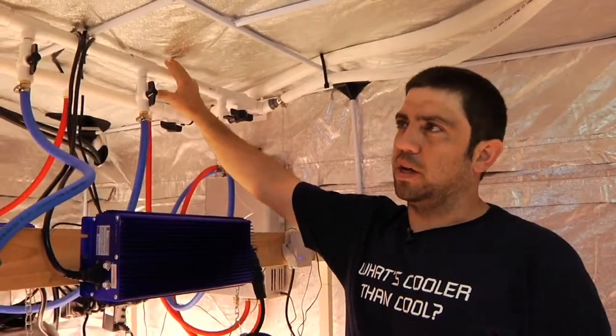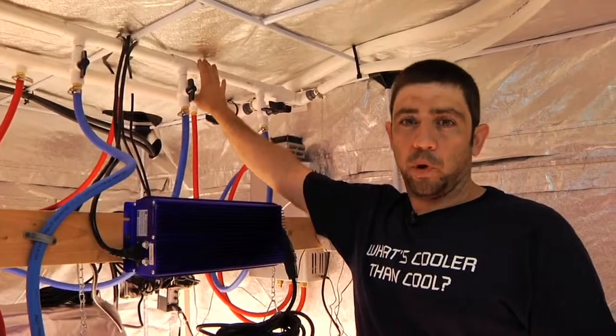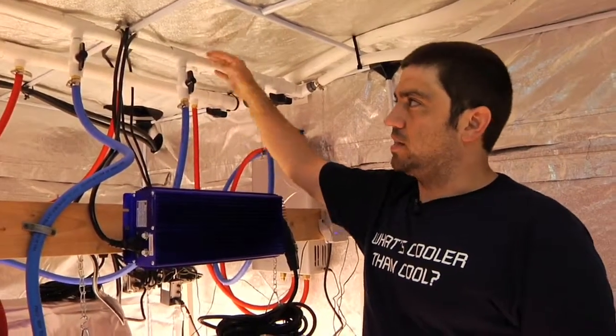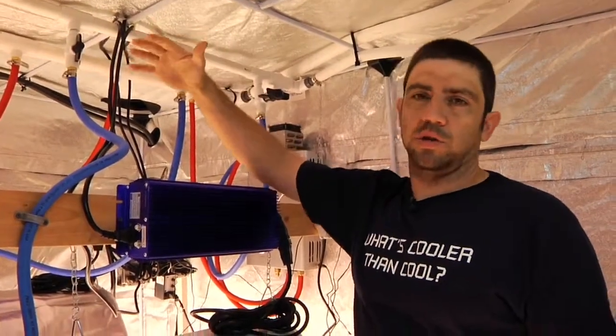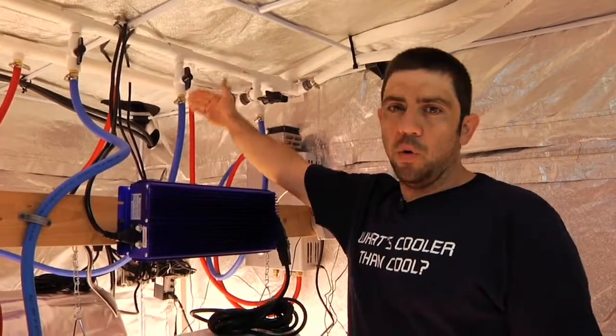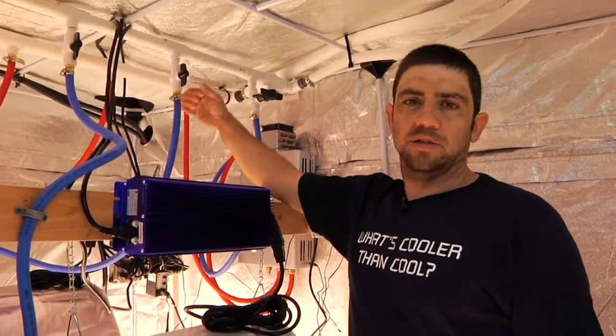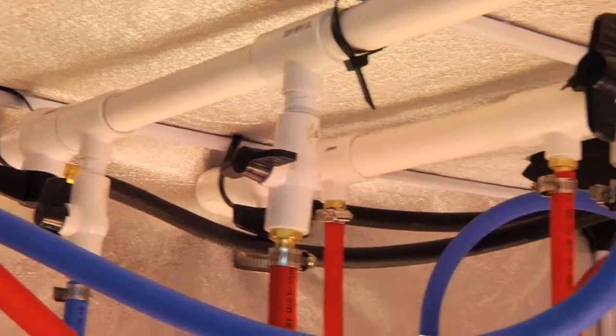And the reason is because we want our manifold pressurized. And the reason we want that is that's what's going to give us even distribution through all the equipment. And we want no pressure on the backside, and that's how the system works. These are properly set up manifolds.